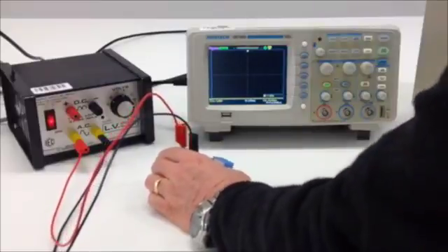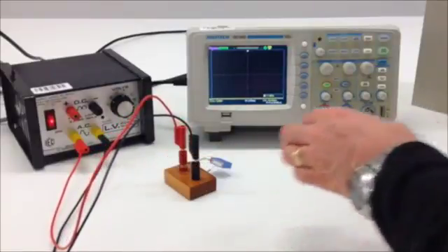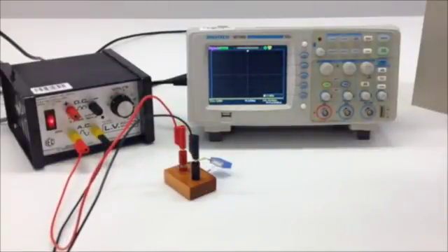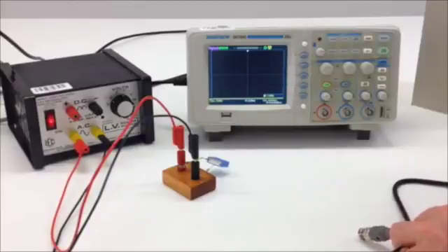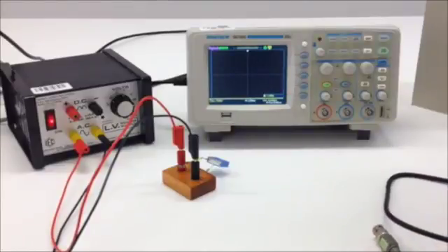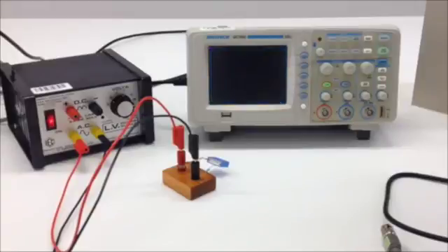Now, to measure the voltages in this circuit we're going to make two voltage measurements using both channels of the oscilloscope. So we will need two probe leads. But an important thing about oscilloscope probe leads is one of the inputs is an earthed input. And so whenever we connect that earth input to a circuit we have to make sure that all earth inputs are connected to the same part of that circuit.